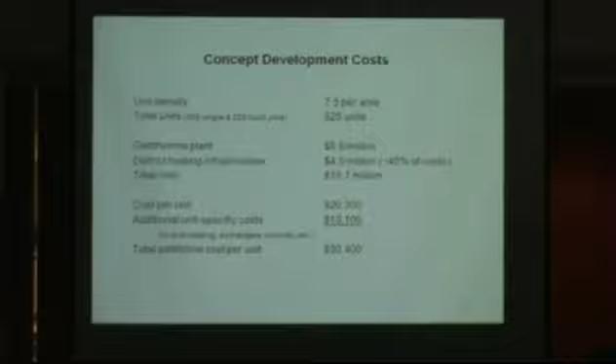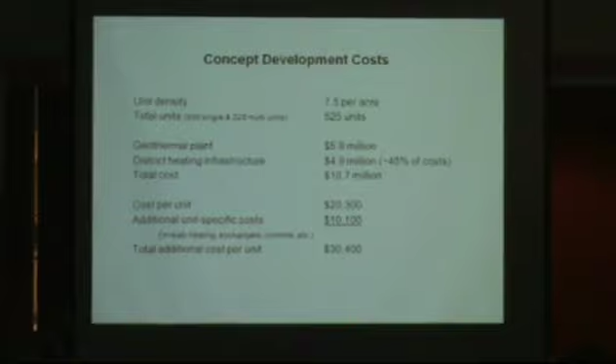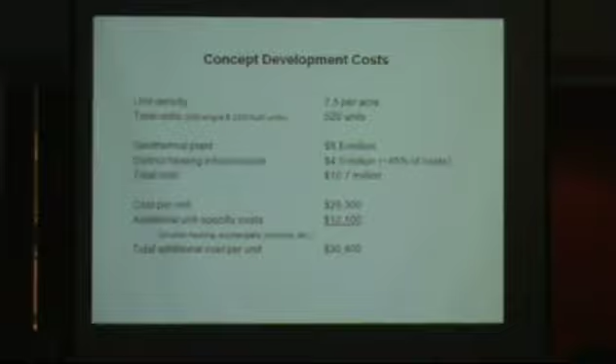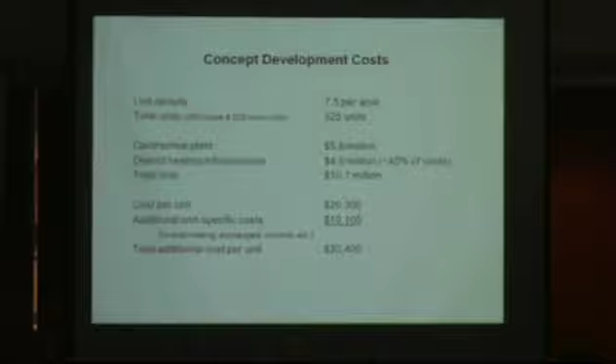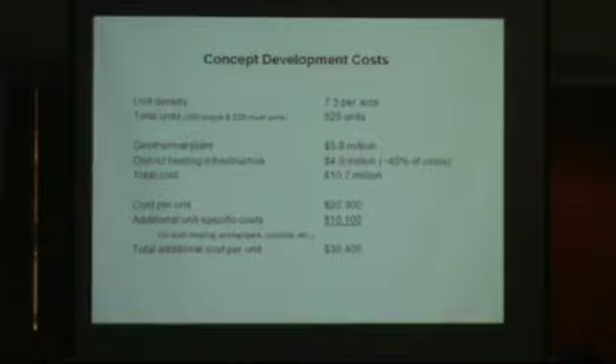The per unit cost of $20,300 represents how much each average household would pay if part of the utility providing this energy. That's the cost the utility, whoever built this thing, would bear. But each individual house or living unit has to have the in-slab heating, exchangers, and controls, costing an additional $10,000 roughly to tie into the geothermal source. So the total cost per unit is about $30,000 to have this.